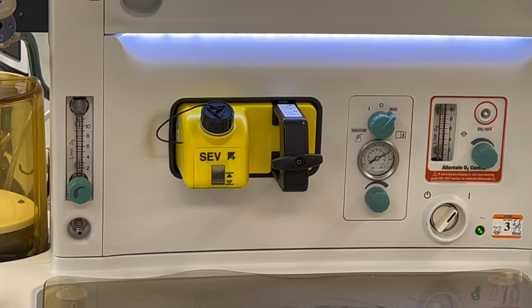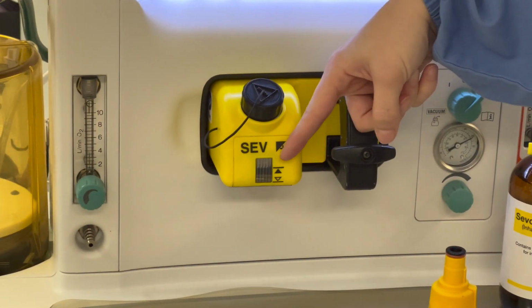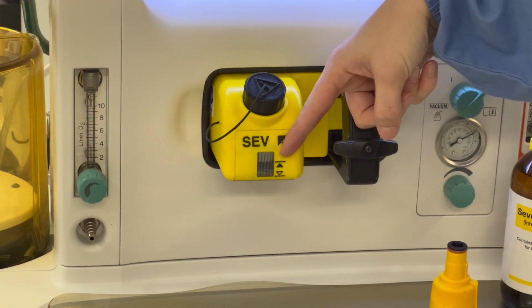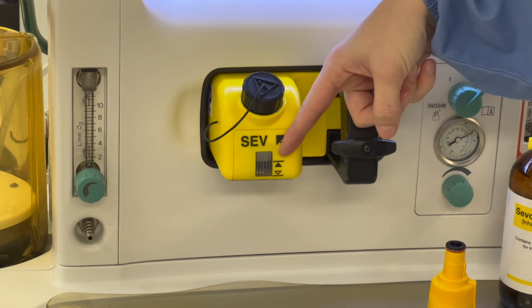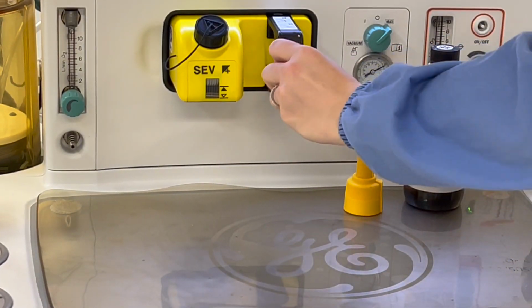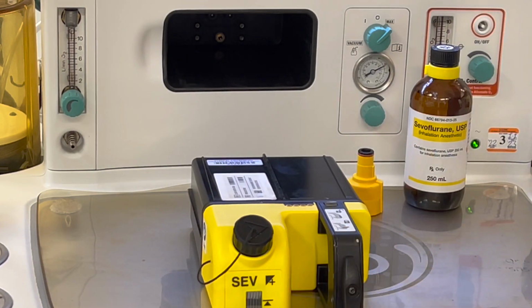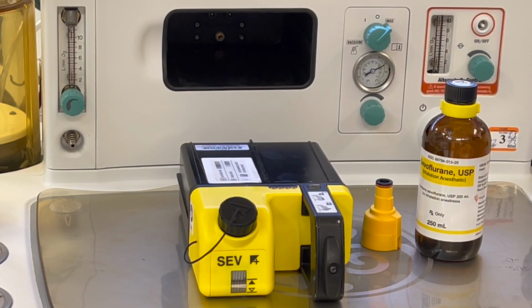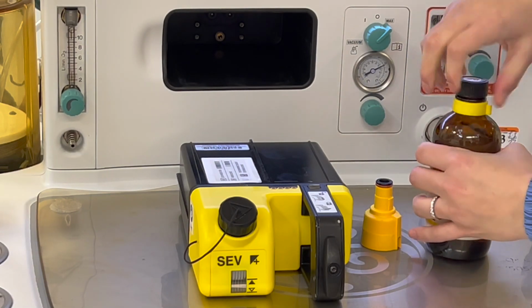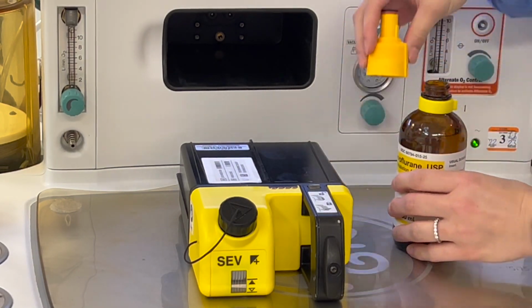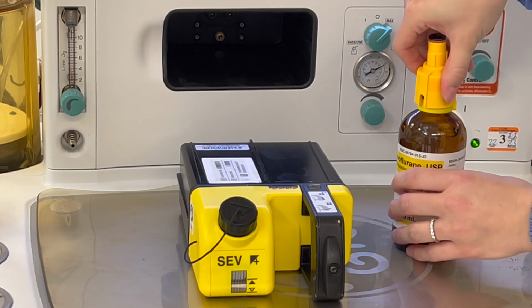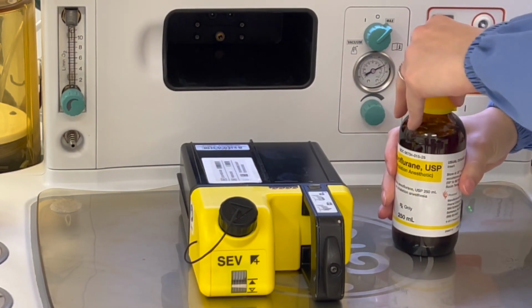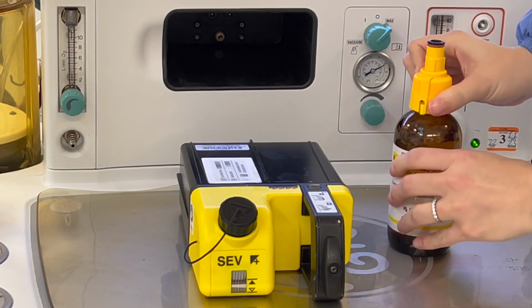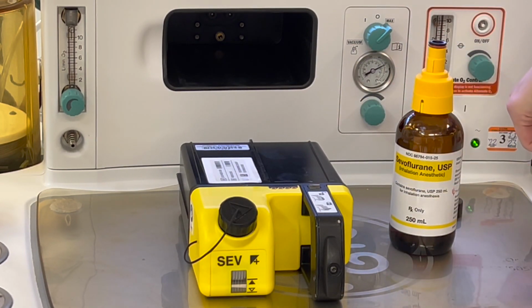This Datex-Ohmeda uses an Aladin cassette vaporizer, and you'll want to check it to make sure that it's full and that the cap is sealed tightly. You'll notice the fill level comes up to the dark line, the black triangle, and this is how you remove it. You twist that knob and then pull the handle. So to refill the cassette, you're going to need the bottle and the special adapter you see here. Remove the cap off the bottle and then place the adapter on. It fits on only one way, and it only fits on this specific bottle of sevoflurane, so as not to confuse it with other gases like isoflurane.